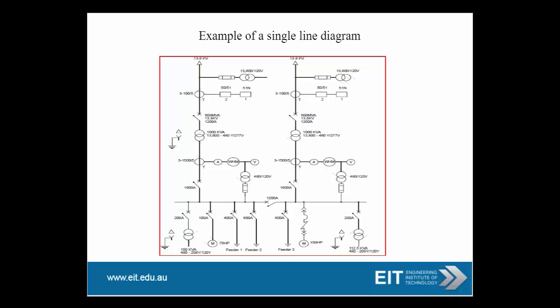You have two incomers and a bus coupler in between, rated at 1200 amps. You have a number of loads — some are transformer feeders, some are motor feeders — different devices and equipment, all shown in a simple format. Pointing out the symbols: that is your fuse and potential transformer, this is your current transformer, that is your circuit breaker, that is your distribution or step-down transformer, that's your CT, circuit breaker, outgoing loads, and this here is your bus coupler.